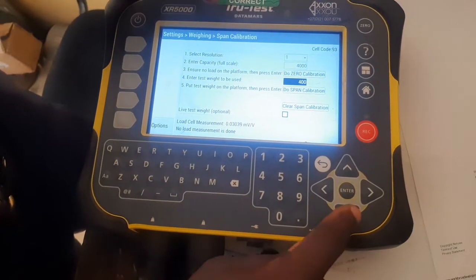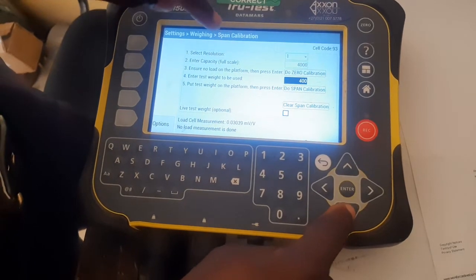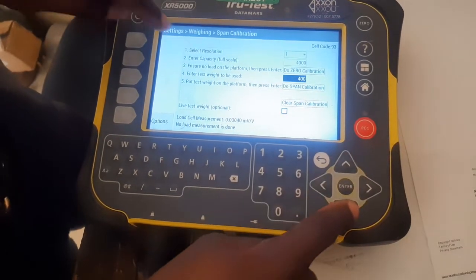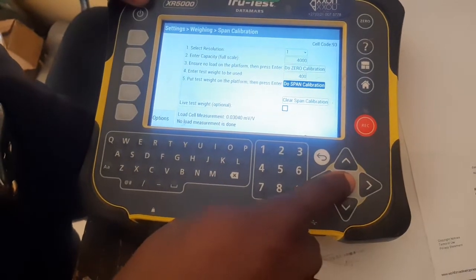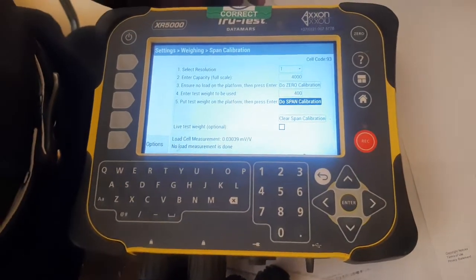When you've keyed in the calibration weight, load it onto the platform. Then go to span and press enter to finish the calibration. Done.